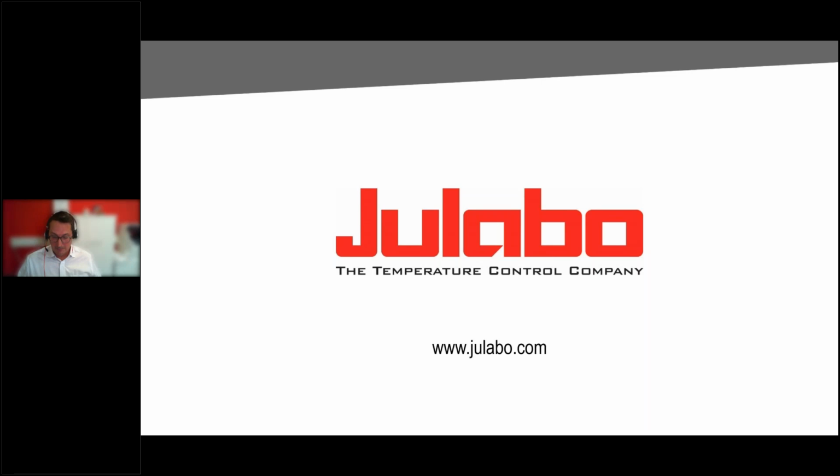I would take this offline and make a specific recommendation, asking what you're cooling. But what I would say very, very quickly is, with minus 20 and an environmental temperature above 25, I don't think Peltier is going to work for you. With frequency control compressors, voltage and frequency is much less of an issue, and it should be possible to have an off-the-shelf product that is portable and usable.